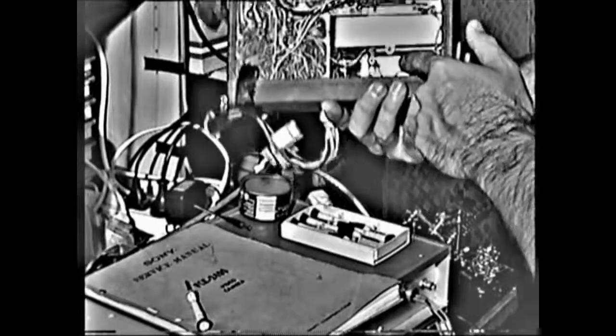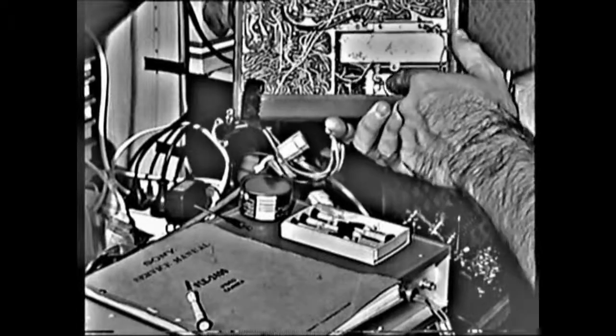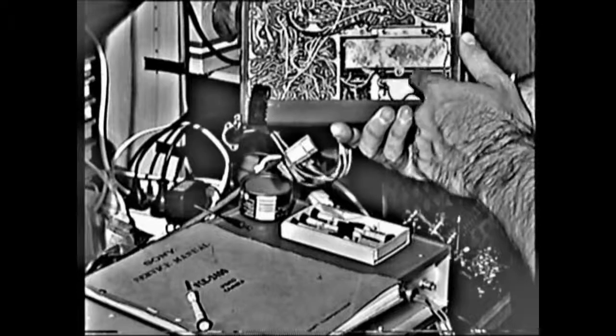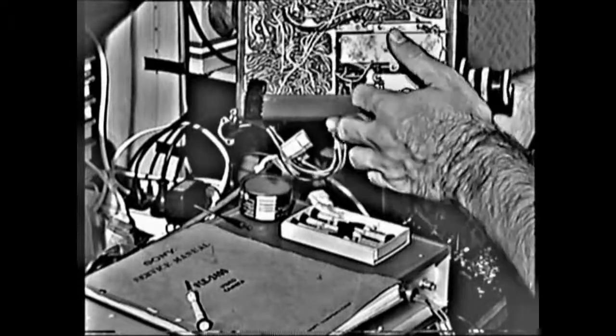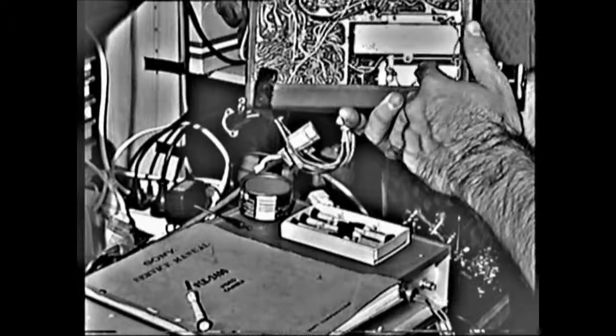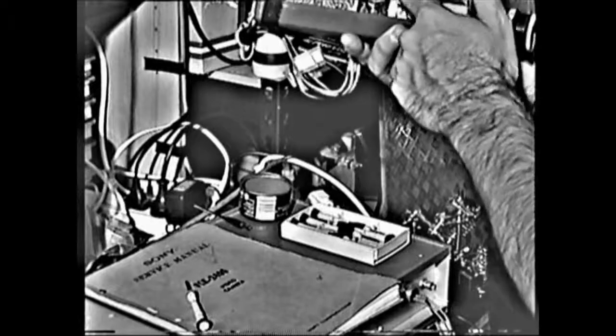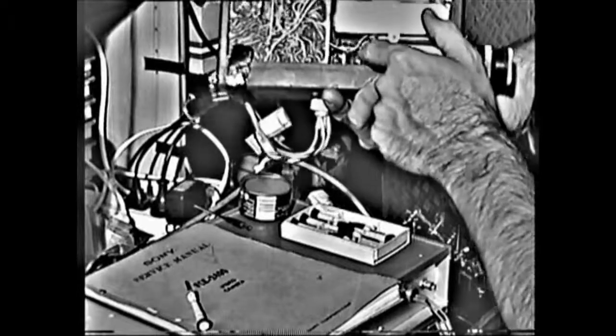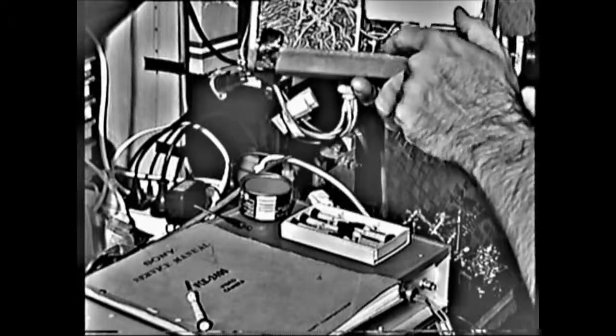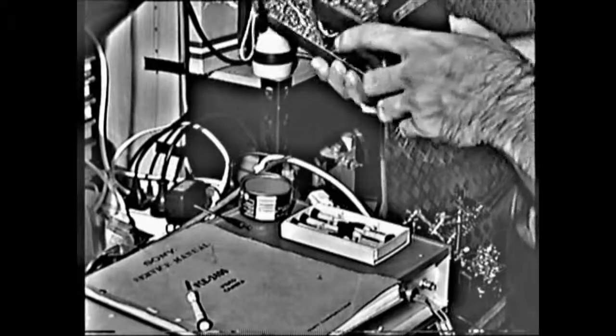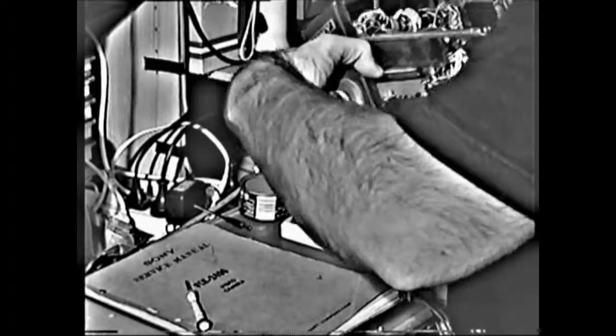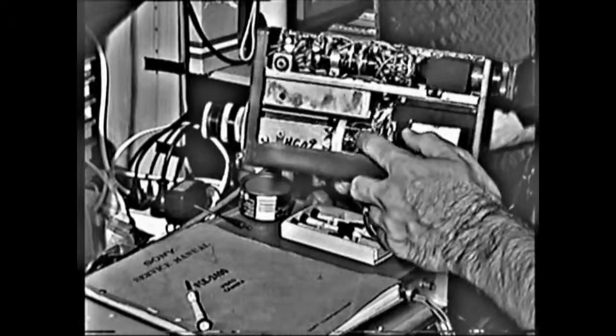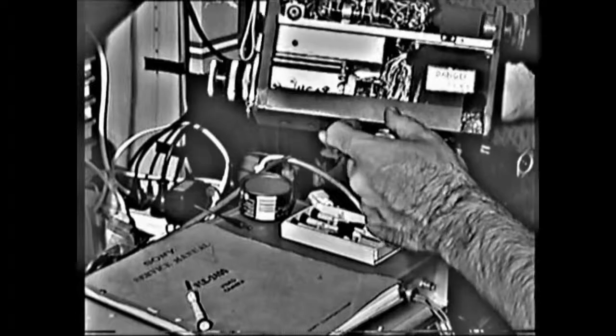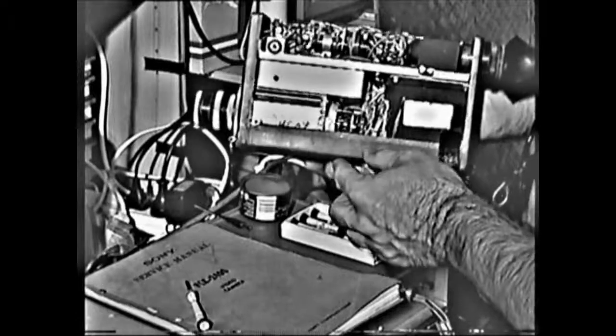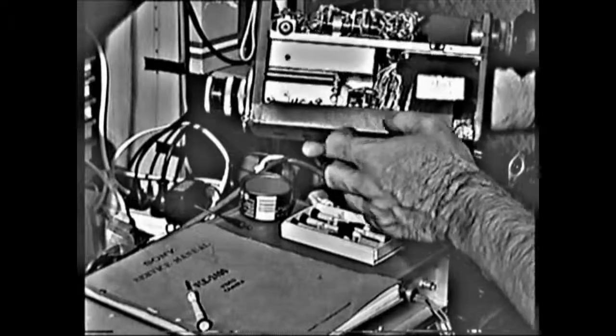That here is the yoke containing the vidicon tube, scanning coil yoke, the horizontal vertical scan coils, and this is magnetically focused, so focus coil as well. The tube's on the inside, so you can probably see the back end of it right there. See it all better from the other side, of course. That's the back end of the vidicon tube, small 2.5 inch, sorry, 2/3 inch vidicon tube.